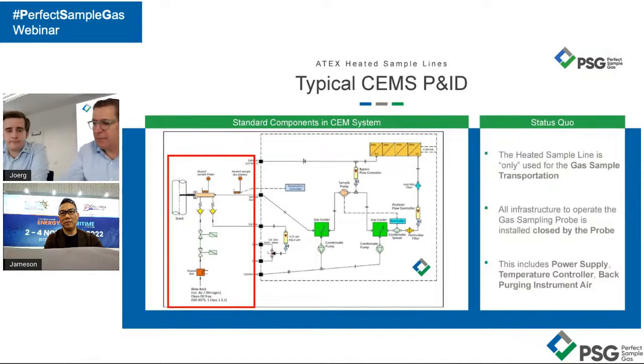This means there can be multiple things: for example, the probe needs a power supply. The probe might need a temperature controller, depending on the controlling technology. We also have self-regulated solutions. A probe might also need a signal for steering the blowback, the back purging.